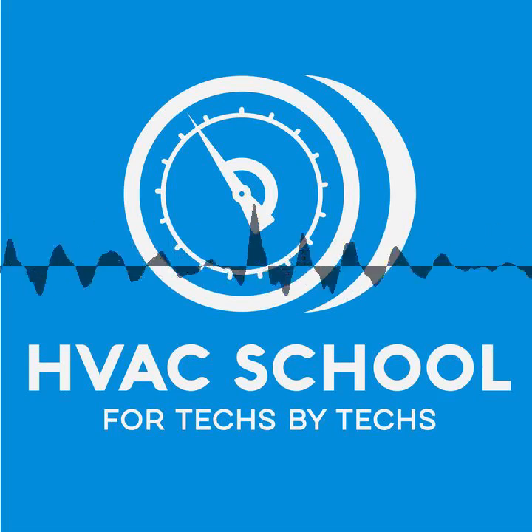I think another part of the issue that makes people upset is this TX valve is like this little black box, and a lot of OEM TX valves aren't adjustable for superheat. In other words, there's nothing to fiddle with. There's nothing you can physically change on it to make it work. So if there is something that's not working, it's pretty easy to see this TX valve and think, oh man, this must not be doing what it's supposed to do because the conditions in my evaporator aren't what I want them to be. The system's not pulling down, whatever. I'm going to change this TX valve out because there's nothing else I can do with it.